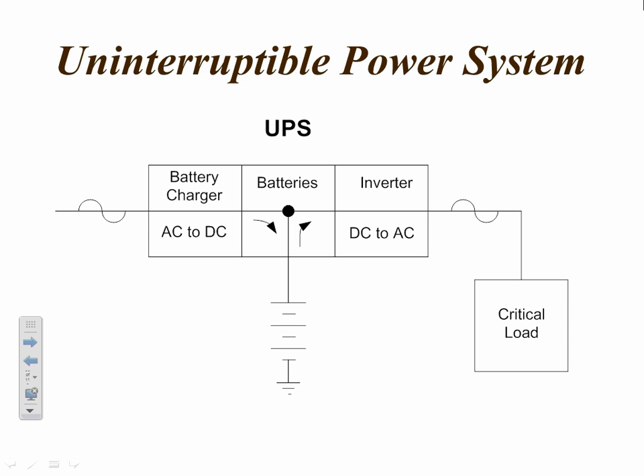And that's true of a small UPS system that you'll buy from a Liebert or PowerWare or people like that. If you want 30 minutes of time, you're going to pay a lot more money for the batteries than you are if you only need 11 minutes of time, we'll say. So basically, most of it's just going to be enough time for them to save whatever they're doing and then be done with it. What IT people call that is we want enough time to do an orderly shutdown. So typically that's how the batteries are sized. But more batteries equals more time. It's just that simple.